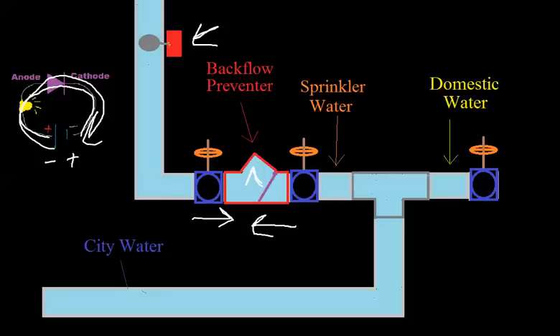And then inside the pipe, there's a paddle. And so when water starts flowing this way, it hits that paddle and pushes it up. And that triggers a switch. It doesn't trigger a switch immediately just because differences in pressure. Sometimes this paddle will move a little bit.